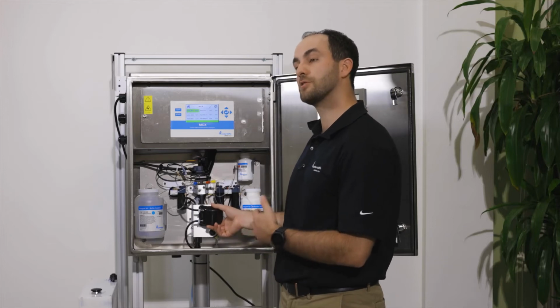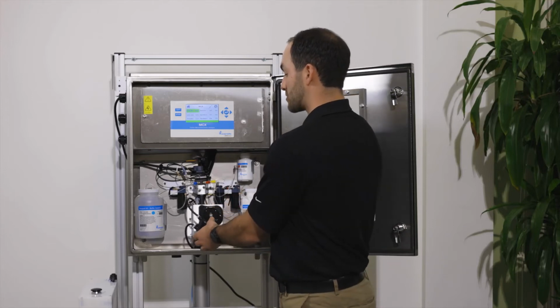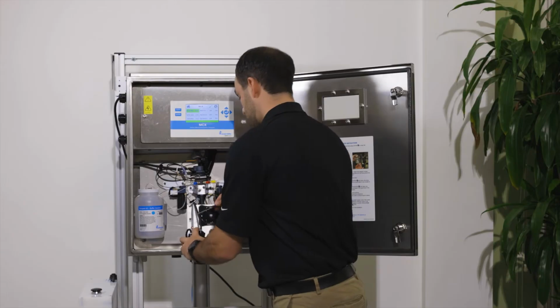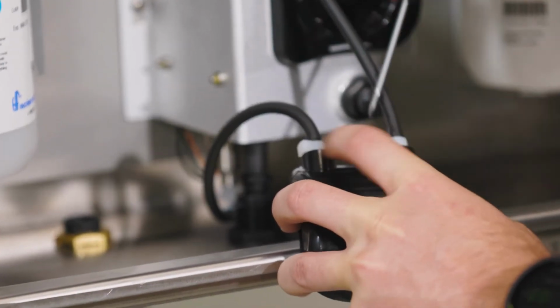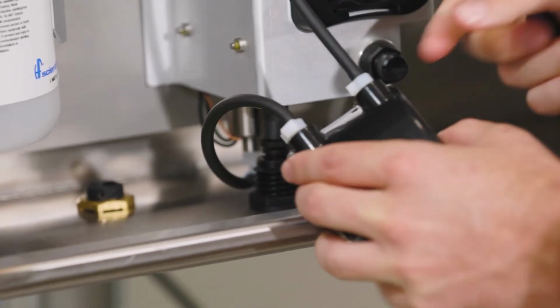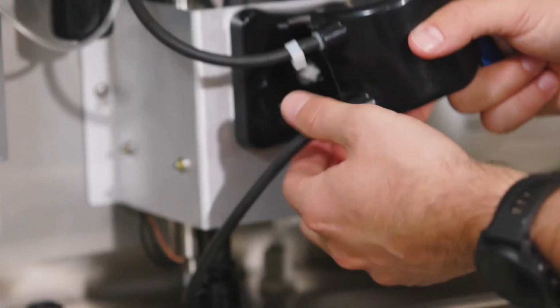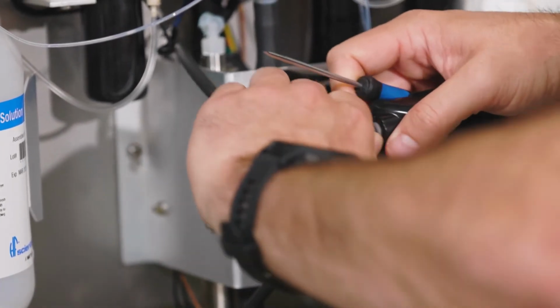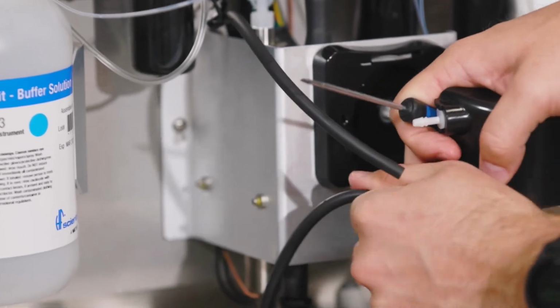Once you have the peristaltic pump head off, you need to take a small screwdriver to pull off the two connector pieces. Pull these back, and then simply pull the black lines off of the reagent.